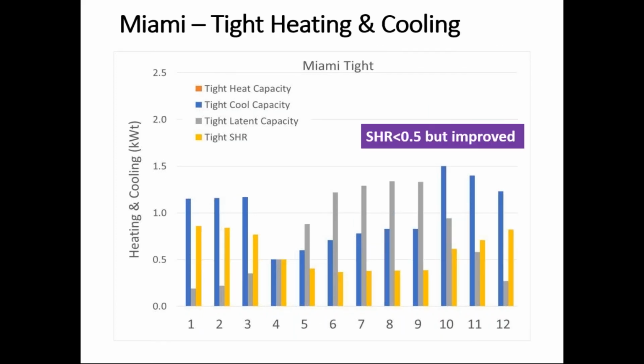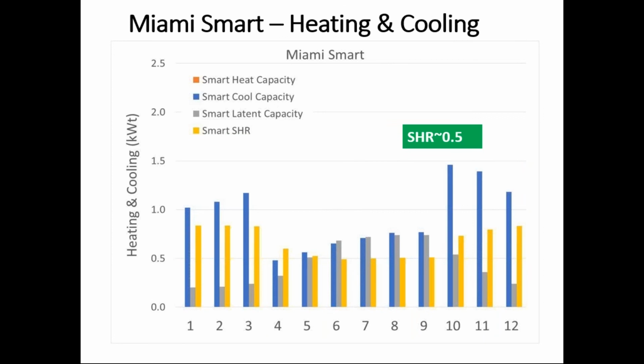When we get to a tight home, but still with quite a bit of ventilation, airflow bringing moisture in, we start seeing the sensible heat ratio start to increase, a significant drop in the latent capacity needed. So an overall improvement, but still significantly low sensible heat ratios where this home as well, it would be wise to add a dehumidifier. And then in smartly ventilating, now, if you added four people to this home, the ventilation needs would go up. If you're having a party, if you have other things going on, the sensible heat ratio may drop below this average sensible heat ratio. As we saw with the daily data, it fluctuates quite wildly.